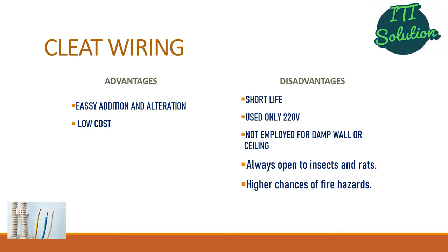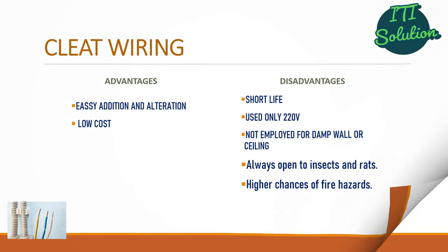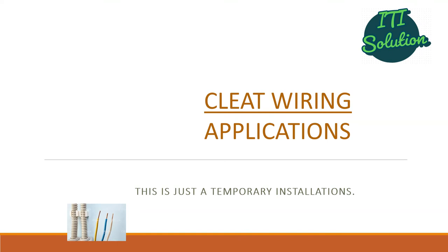Advantages of cleat wiring are easy addition and alteration, and low cost. However, there are many disadvantages: short life, used only up to 220 volts, not employed for damp wall or ceiling, always open to insects and rats which can cut the insulation of wire, and higher chances of fire hazards. For applications, this is just a temporary installation, not used so much — only used in initial times of construction to obtain electricity.